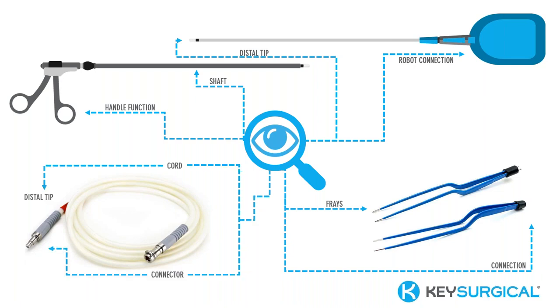Again, the cord is not an insulated electrosurgical instrument, but cords can be associated with fire. They do have this insulation on them that needs to be inspected along with the distal tip and the connector. They are important tools in electrosurgery procedures.